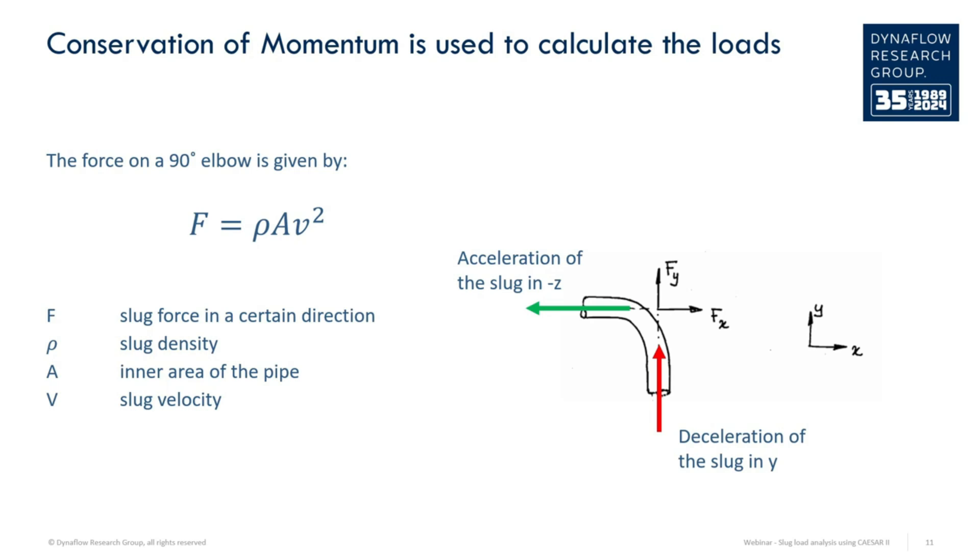Note that since the velocity is squared, an increase in flow rate greatly increases the forces in the model. The second force is due to the acceleration of the slug in the other direction, pushing back on the pipe where it came from.